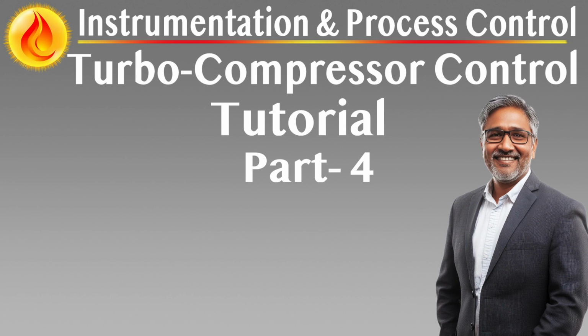Human-machine interface, HMI, real-time visualization, diagnostics, and control interface for operators and maintenance personnel. The human-machine interface, HMI, embedded in the Turbo Compressor Control System, TCCS, is the primary window into compressor and turbine operations. Designed with intuitive navigation, real-time updates, and layered access security, the HMI allows operators to monitor, interact with, and diagnose the turbo compressor package efficiently and safely. It provides interactive graphical displays, alarm handling, trend analysis, and report generation, while ensuring no control actions are dependent on the HMI, guaranteeing uninterrupted compressor functionality even if the HMI fails.